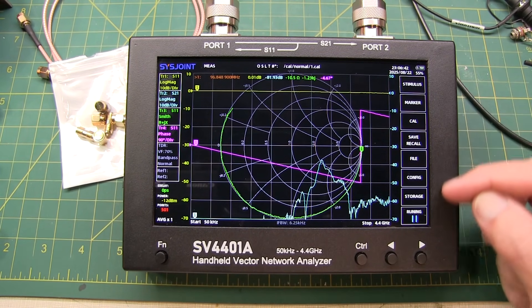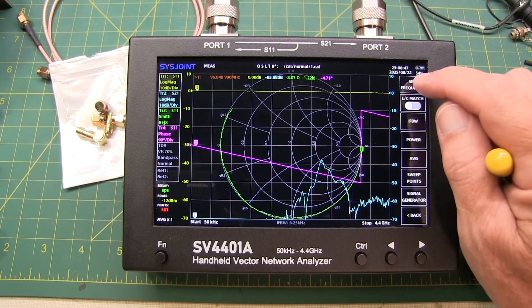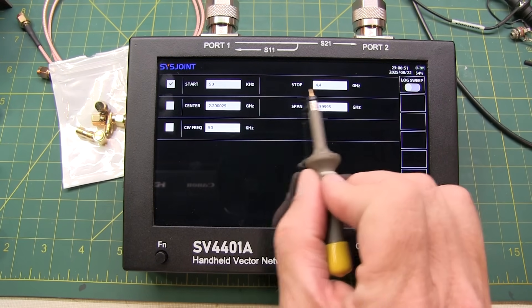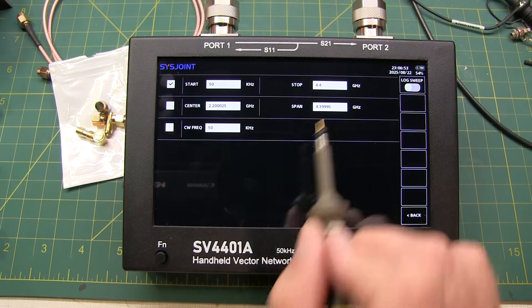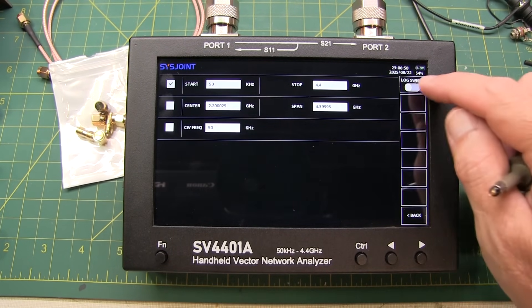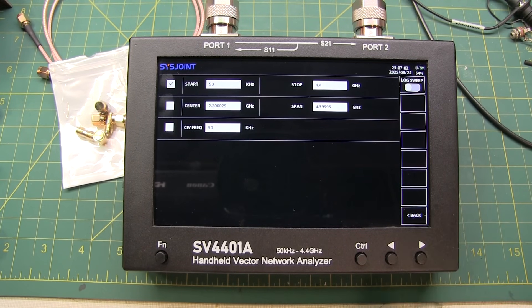Now the main menus on the right all kind of start at this level. The stimulus menu will give you the ability now of setting the frequency through either setting the start and stop, or the center and span, or just set a CW frequency if you're doing some CW testing. And you can even set up a log sweep. You hit back to get back to the main menu.